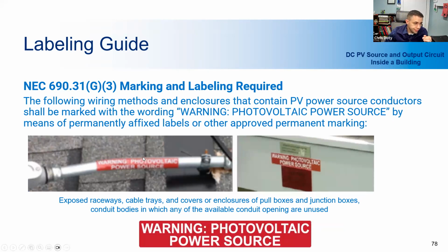So here we have the PV power source labels. You want to have all of the DC conductors that are in metallic raceways or metal clad cable inside a building labeled. They all have to have this labeling: Warning, PV power source, at a minimum every 10 feet. Many people don't like the look of this, as you might expect, but it's code, so they have to deal with it. A way around this is to run the conduit through the attic space or use microinverters at the solar panels, which convert it to AC power, which can then be run through conduit without this label, so that they can avoid having to see this red label.